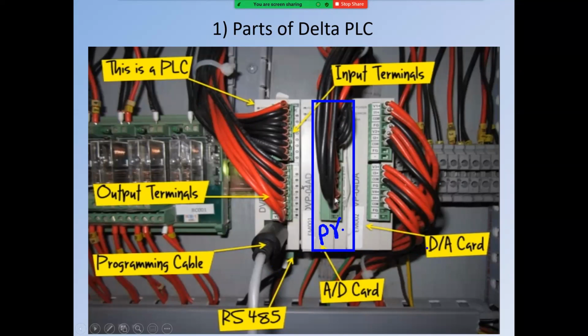Why do we require this? Because sometimes your controller is not digital, meaning on and off only. Your controller might be a pressure control valve, which requires 4 to 20 milliamps of current. This current varies from 4 to 20, and this is an analog signal. But in the case of digital, it's either on or off, meaning 24 volts or 0 volts. Both types of signals have to be handled in this PLC.